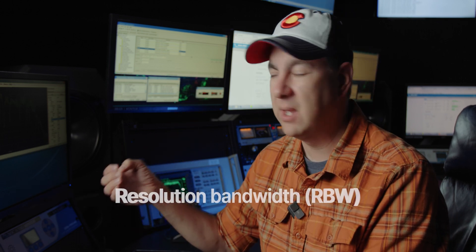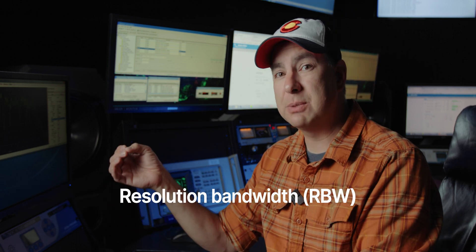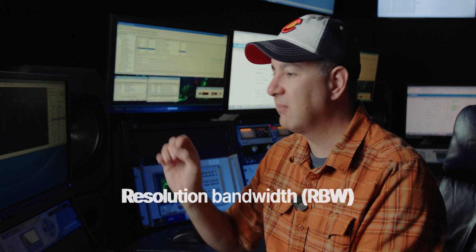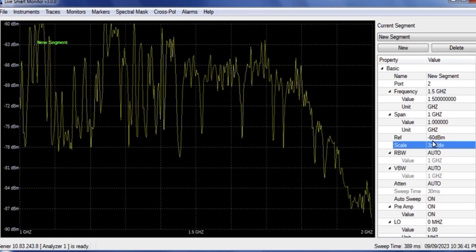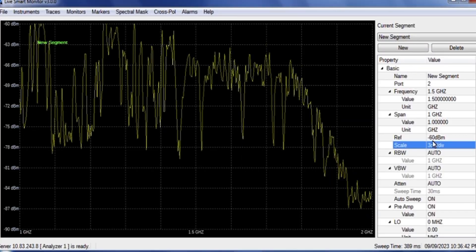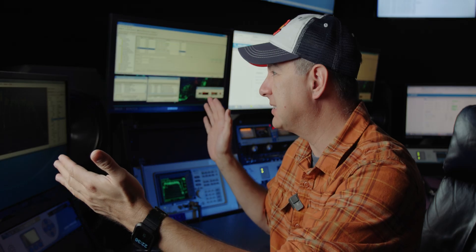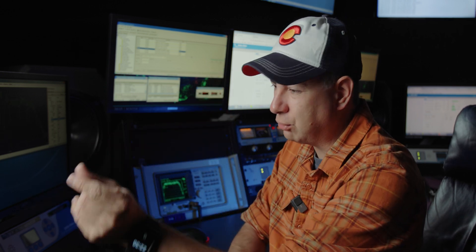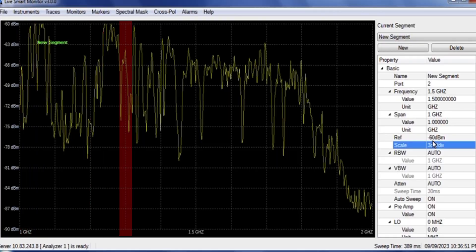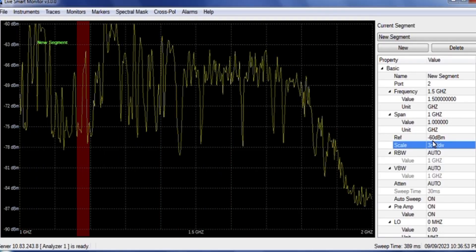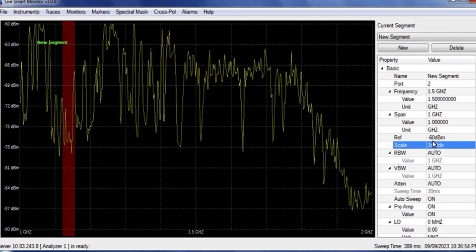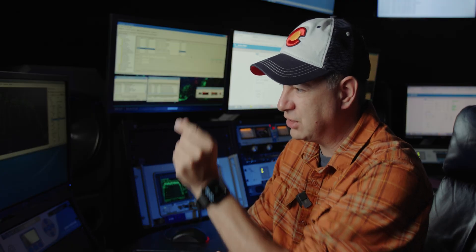The resolution bandwidth is basically a filter window. We're looking at this whole big piece of RF. In this case, it's about one gigahertz of RF. And you have this window that slides across this span of one gigahertz right now. And as it goes across, it goes into each individual slice. And it'll read the RF in that one slice, plot it on the screen, move to the next slice, plot it on the screen, and on and on down the road, down the spectrum that it goes.